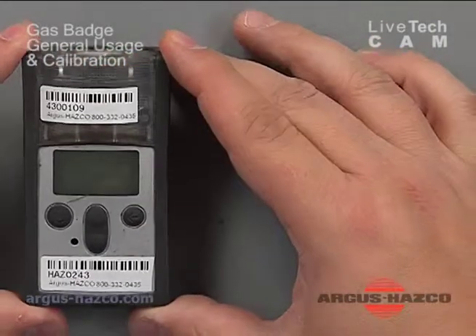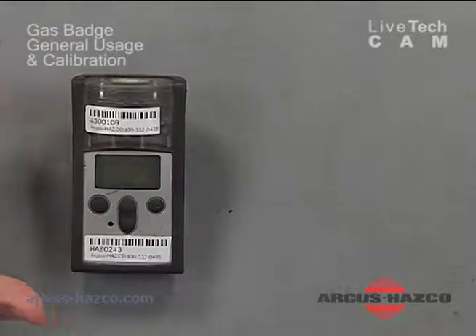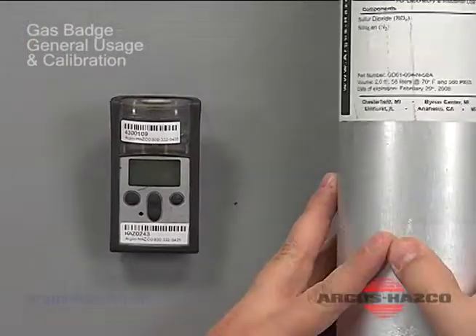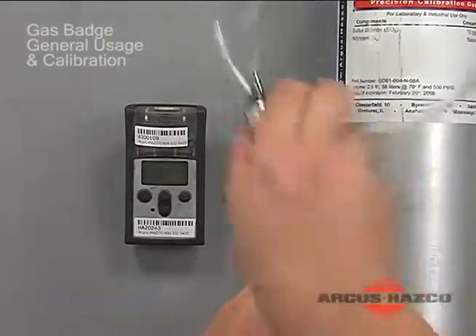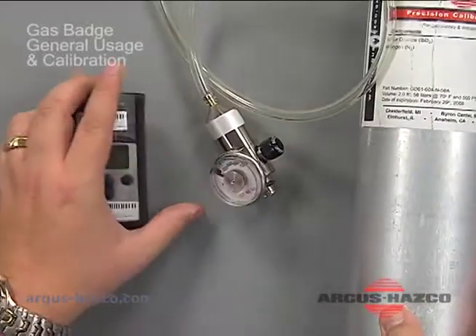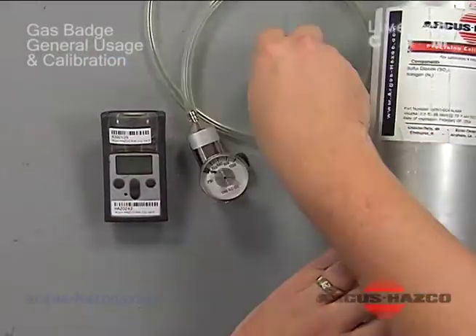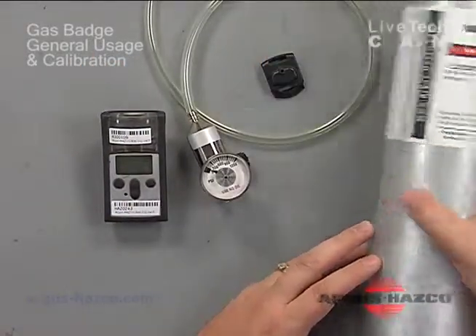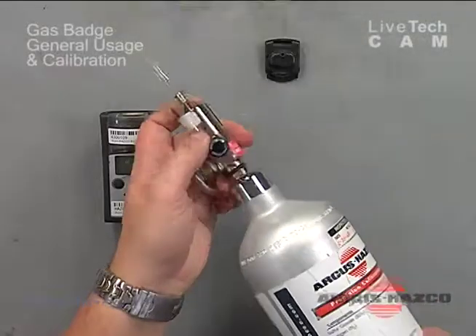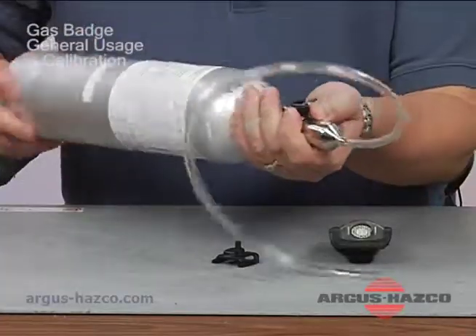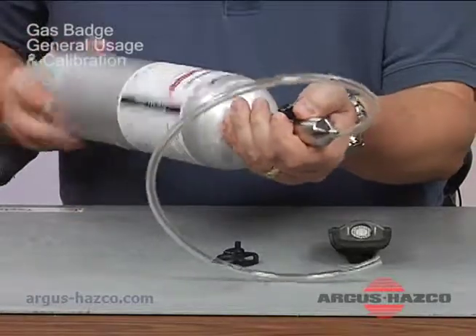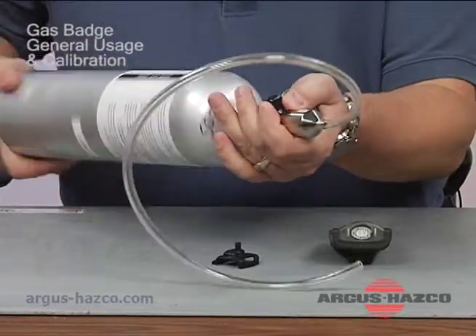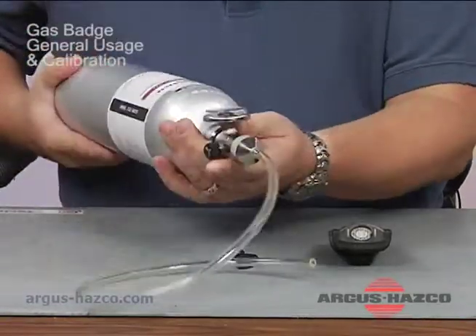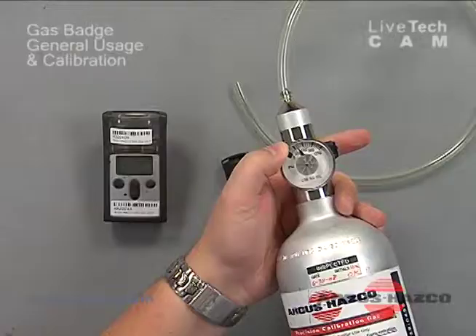So we have the Industrial Scientific. You'll need your cylinder of calibration gas, and you'll need a regulator and tubing and your cal adapter. So at this point, we're going to screw the regulator onto the cylinder. You can tell at that point that we do have pressure.